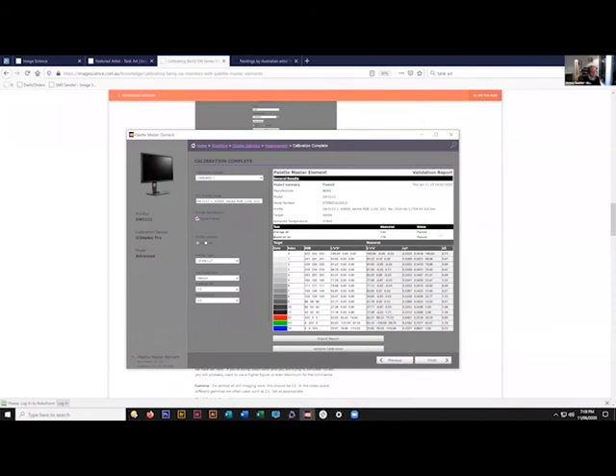And I think a lot of that comes down to the fact that I am absolutely ruthless about cleaning other calibration and color-affecting software off those machines before I start, and that's why all our calibration guides emphasize that really strongly right up front. But you can see here these results are excellent. All of these values are well below even the minimum threshold of 2, and certainly way below the maximum threshold of 4. So we had no trouble at all calibrating, even though we're sharing screens and so on. That's a really good result.